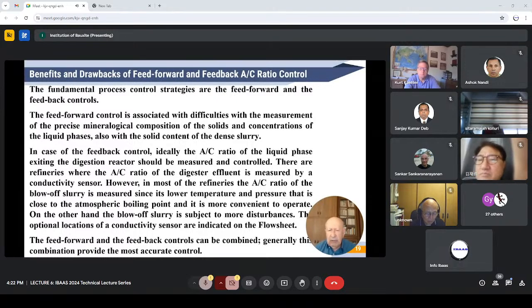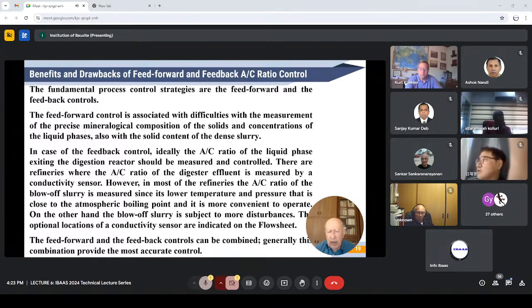There are refineries where the alumina to caustic ratio of the digester effluent is measured by a conductivity sensor. However, in most of the refineries, the A to C ratio of the blow-off slurry is measured since its lower temperature and pressure is close to the atmospheric boiling point, and this is more convenient to operate. On the other hand, the blow-off slurry is subject to more disturbances. The optional locations of a conductivity sensor are indicated in the following flow sheet. However, the feed-forward and the feedback controls can be combined. Generally, this combination provides the most accurate control.